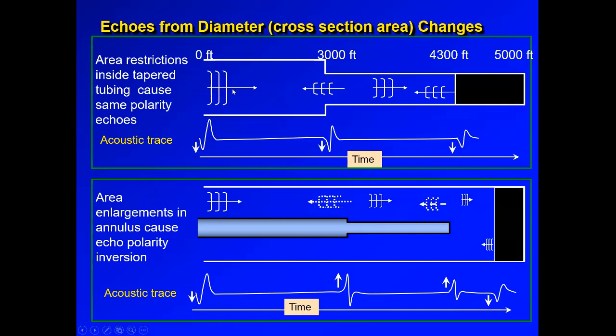So in this example here, the top of this plot, we shoot a fluid level. There is a change in diameter. There is a decrease in this ID. So going down, you have a down kick from the shot. There are no changes in diameter until here. We have a decrease in the cross-sectional area, so some of the energy is reflected off this decrease in diameter. That's actually a down kick that reflects the area. The rest of the energy keeps traveling down until it finds another change in diameter, which is actually a down kick from the liquid level. So we see a down kick from the liquid level as well. So it will be a down kick from any decrease in cross-sectional area, also a down kick from the shot.